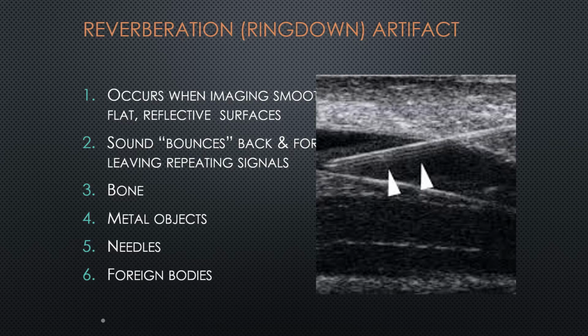So when the sound comes down, gets through the tube, bounces back off the wall, and then escapes back to the probe, that would be the first line. If it bounces back and forth twice, second line. If it bounces back and forth 3 times, third line, and so on and so forth. So that's why we get this ring down artifact, especially from metallic needles.